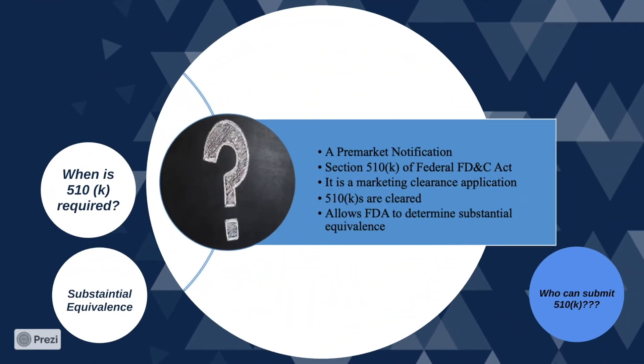Moving on to 510(k): what is a 510(k)? A 510(k) is a pre-market notification. The reason it is referred to as 510(k) is because it refers to Section 510(k) of the Federal Food, Drug and Cosmetic Act. It is a marketing clearance application, and 510(k)s are cleared when FDA determines the substantial equivalence of the device.